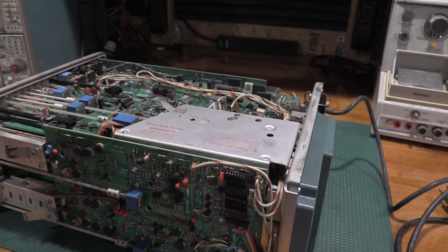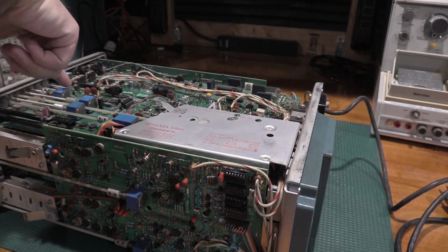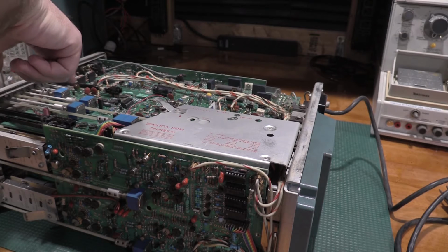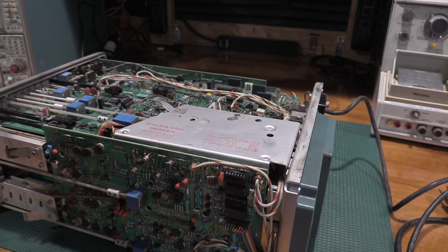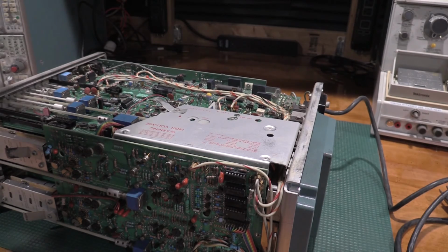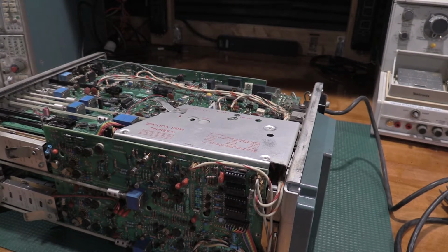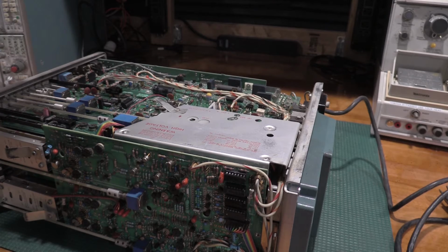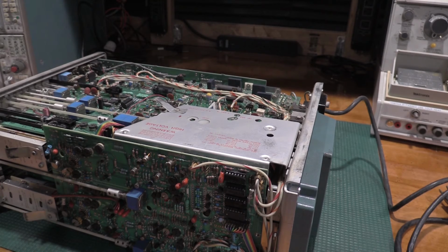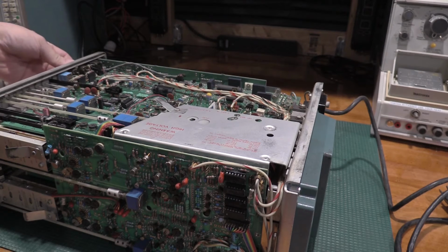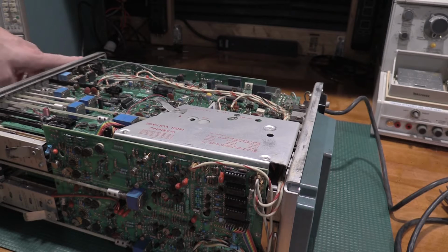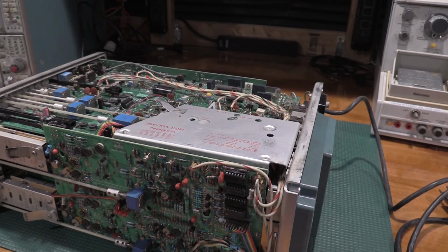Get everything patched up. That's a huge tantalum capacitor right there. He may be due up for a timely replacement. We'll see what he's doing. But yeah, nothing's screaming at me saying I've got problems. So we'll give it a very, very close inspection, and then we'll service up the controls, and then see what we can do on a calibration on this thing. See if it's got any other issues we have to take care of.